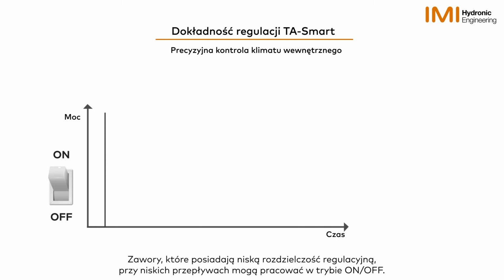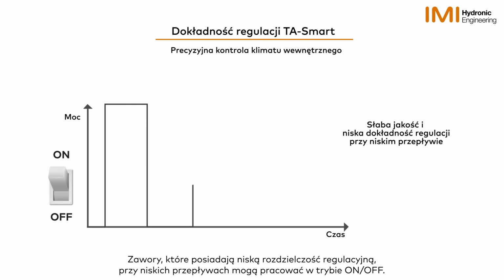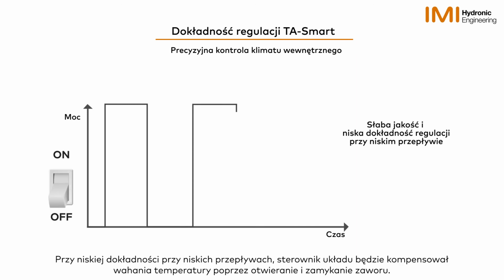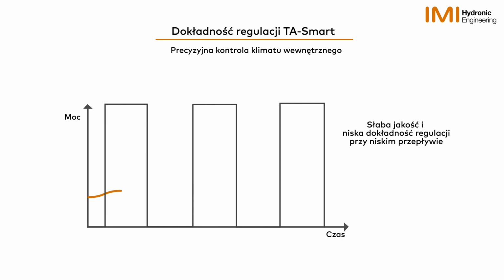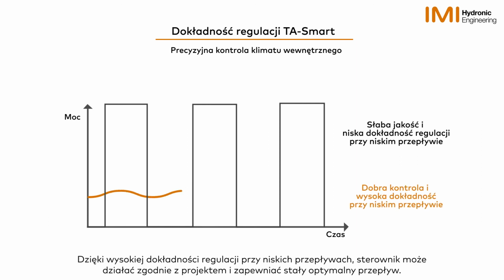Valves that perform badly at low flows risk operating in an on-off manner. With poor accuracy at low flows, the system controller will compensate for temperature fluctuations by opening and closing the valve. With high accuracy low flow regulation, the system controller can operate as designed and deliver a consistent optimal flow.